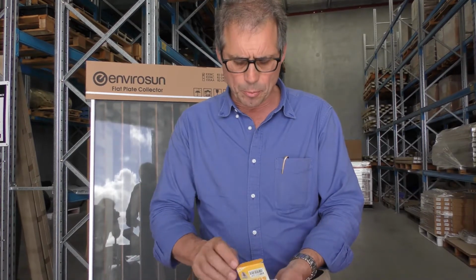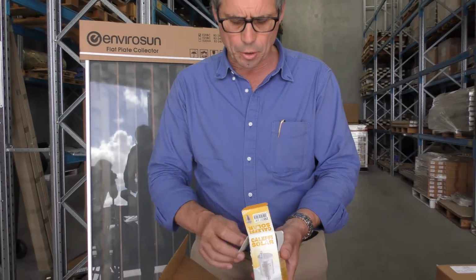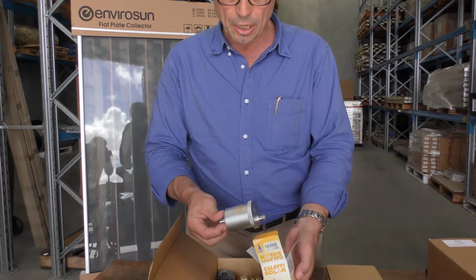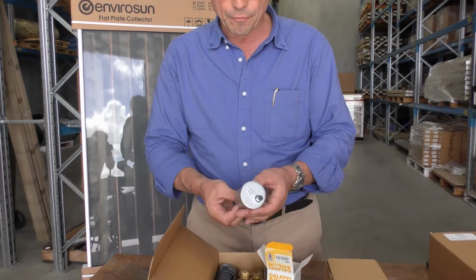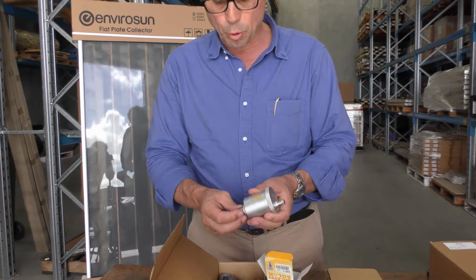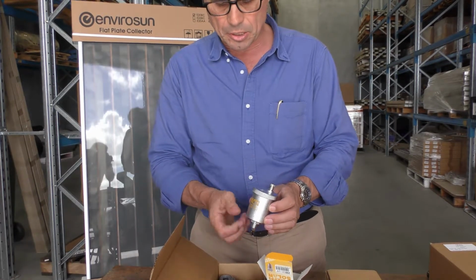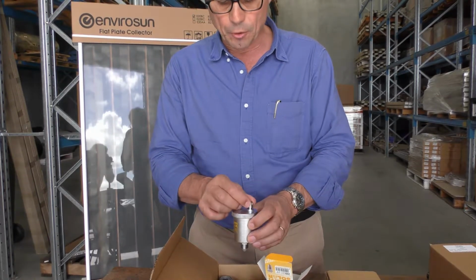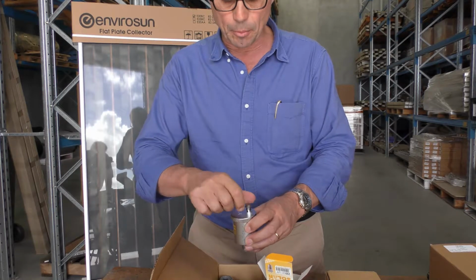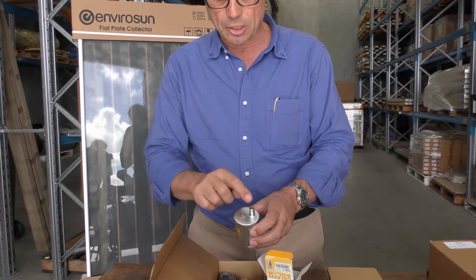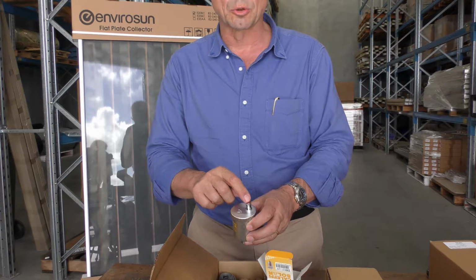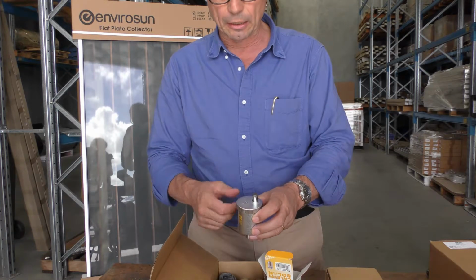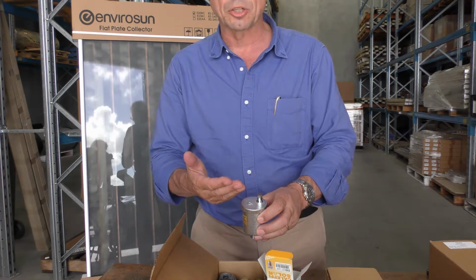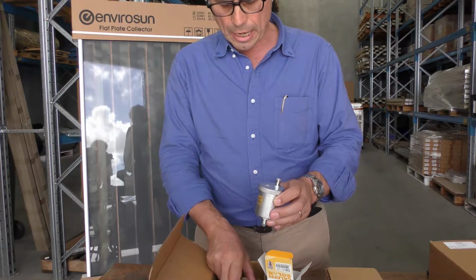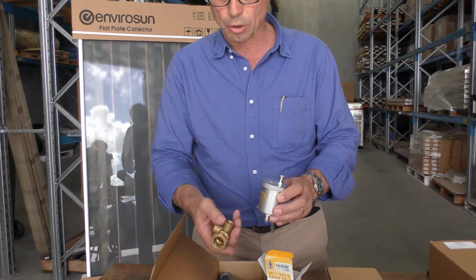So what we do is we provide this as a standard with each of our products. It's a high temperature Caleffi air vent valve. What you've got to do is when you put it into the system, then I'll show you the particular connection that we use later, you've got to crack the top of it to allow the air to come out. So each of these have always had this screwed up. So you just need to crack that and allow, so that will always stay open once you leave it, and it's connected onto this device which we call a HotCon connection.